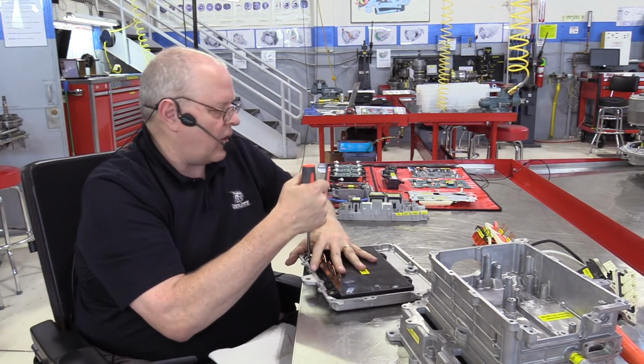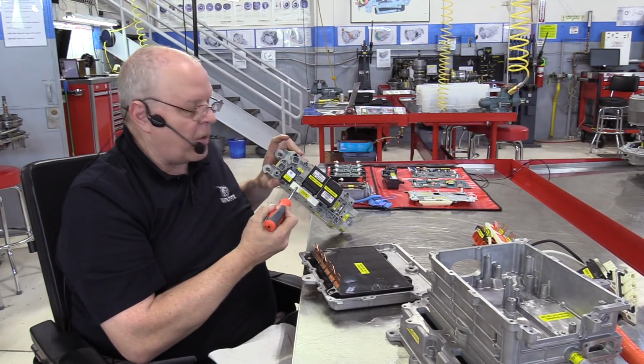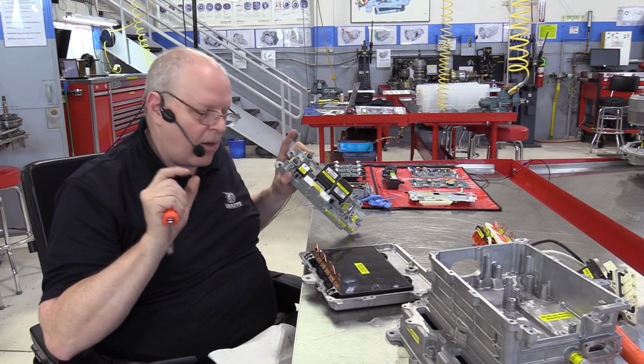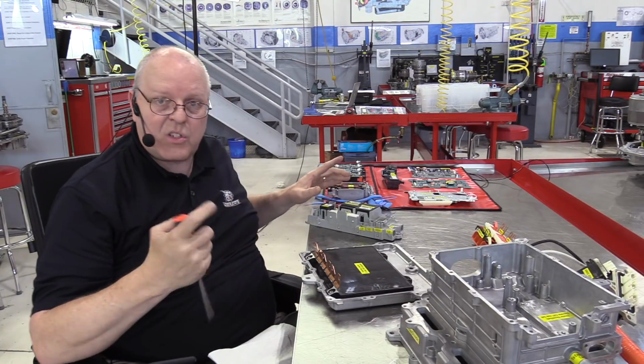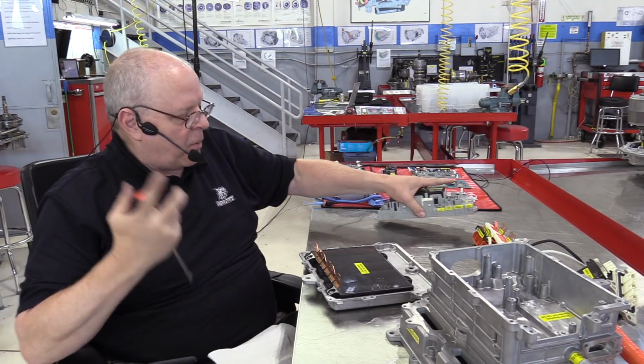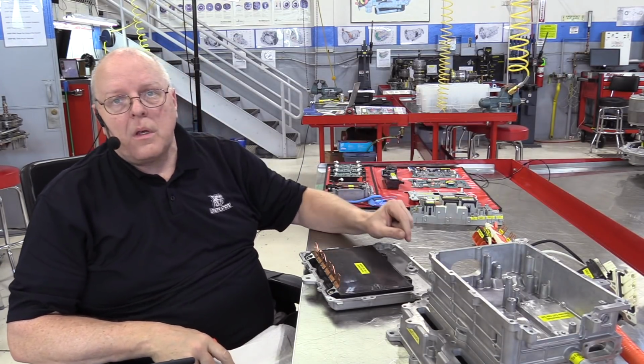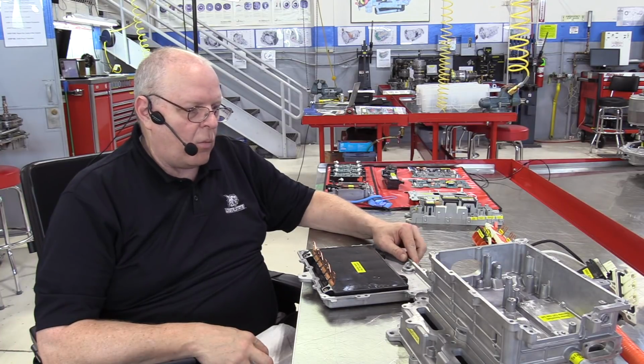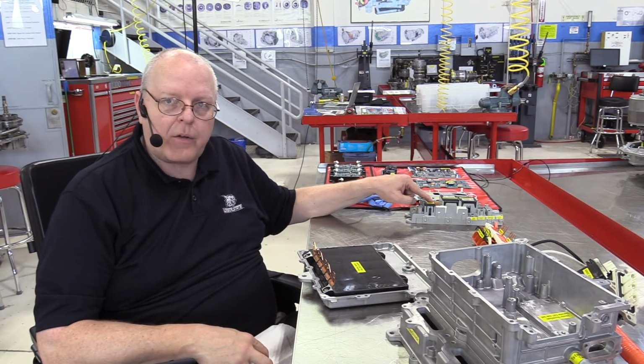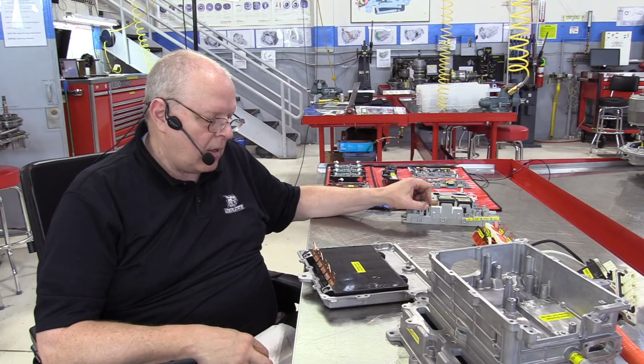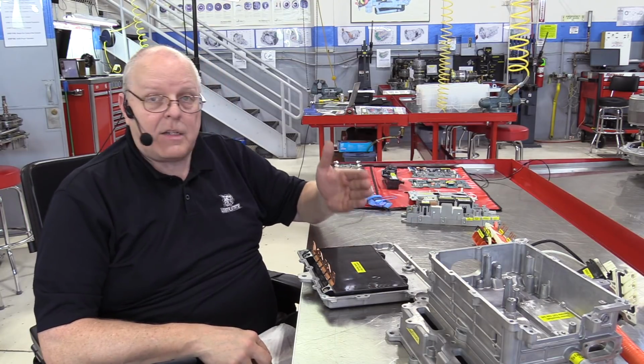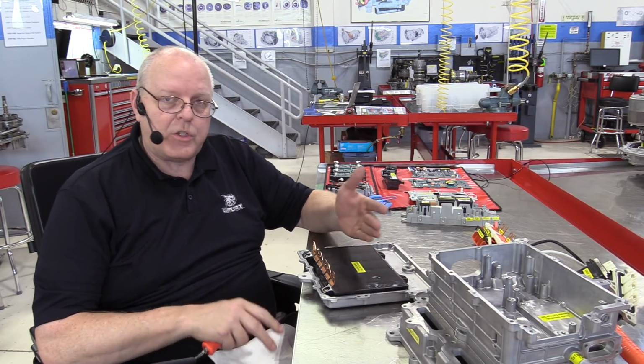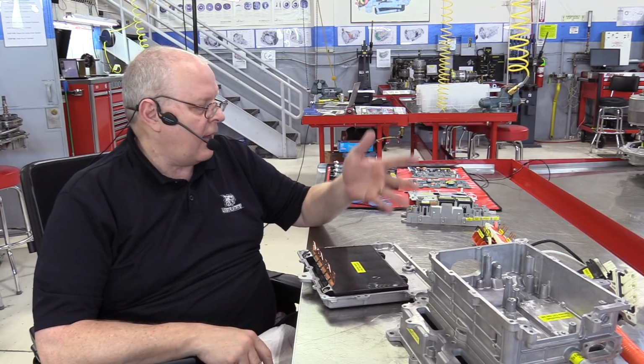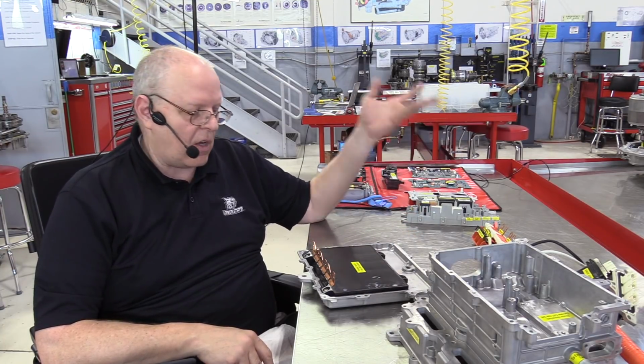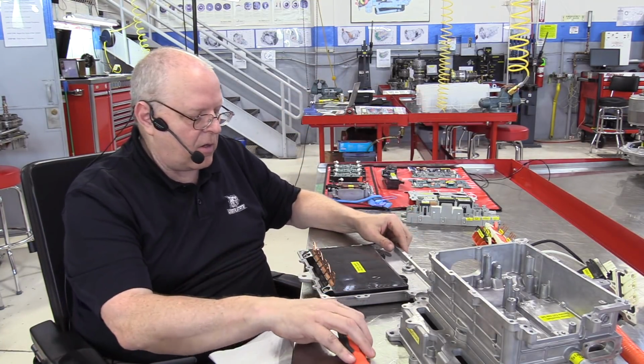So the pre-charge contactor through the pre-charge resistor limits the current down to such a small amount. It's around 6 amps instead of upwards of 100 amps, so it won't ruin the pre-charge contactor contacts as they close. And as I said, when the smoothing capacitor gets fully charged, there's no current in the circuit, and you'll have 0 volts on each side of the negative contactor.